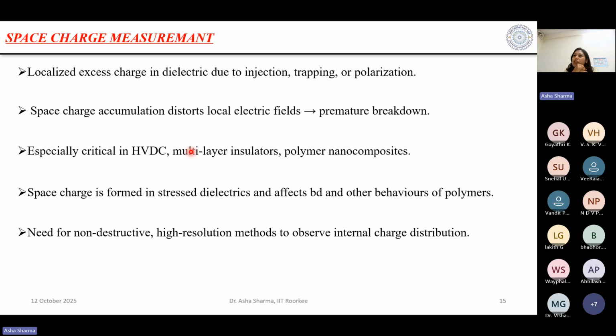In the case of the cable, we use XLPE as the insulating material. This insulation is not perfect. It may again have some defects. It may have some voids. It may have some other foreign particles which are present within the system, right? A partial discharge must be happening over there.